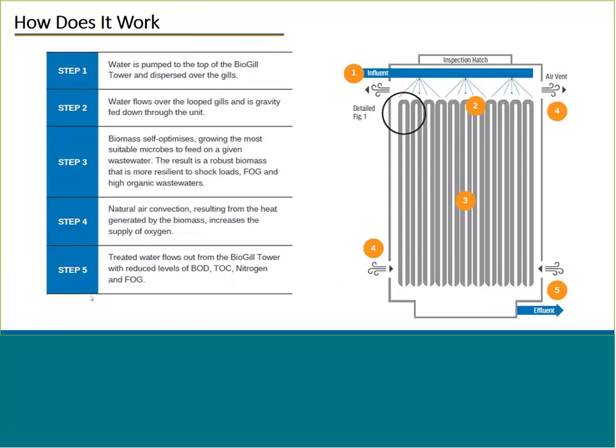I'd like to start with answering the question of how it works. The BioGill Tower is an attached growth bioreactor. At the top, influent flows over our gills, as we call them. The gills are manufactured as a ceramic-coated fabric, the ceramic adding the capability for rapid startup and strong biomass attachment. The influent is sprayed by a distribution system over these gills, flows down where biological treatment occurs, and exits the bottom. On one side of the gill we have air, and on the other side we have water. The air goes in by natural convection and exits at the air vent on the top.